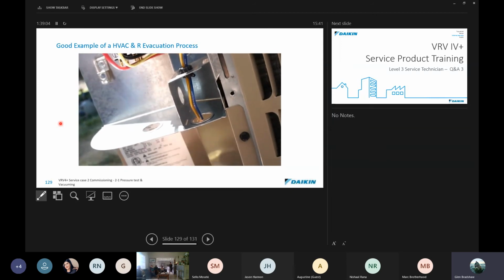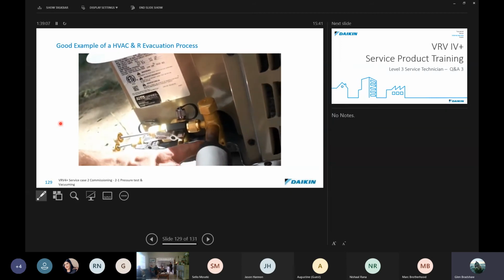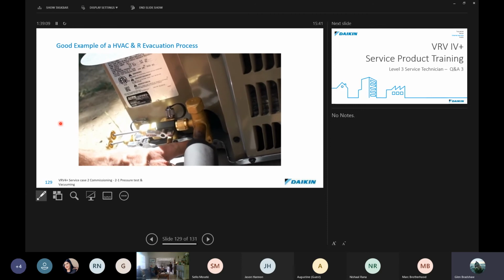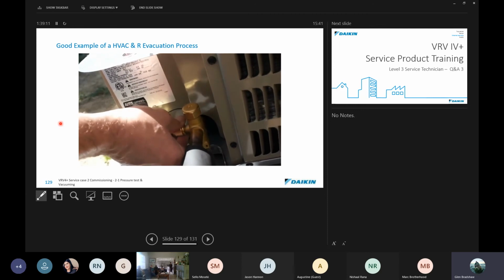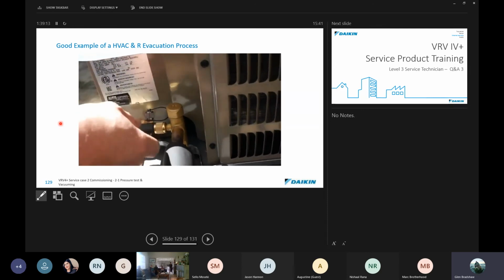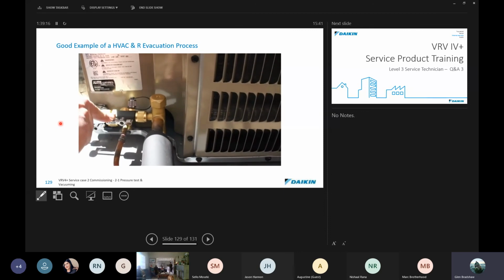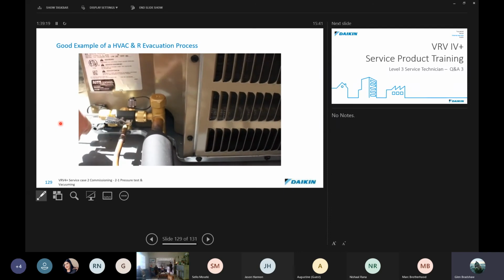All right, so I was fighting these core tools, getting them on here because there's just not a lot of access the manufacturer put in this unit. So what I had to do is take the 2 screws out of the bottom of the service valve here and lift this up a little bit to get it in there, because you want to be able to pull these cores out, because the cores are a huge restriction when you're doing your evacuation.